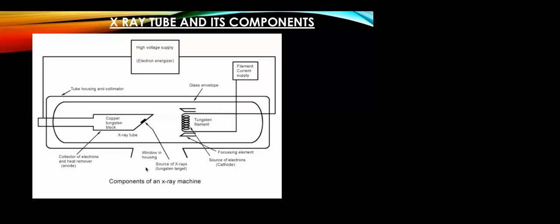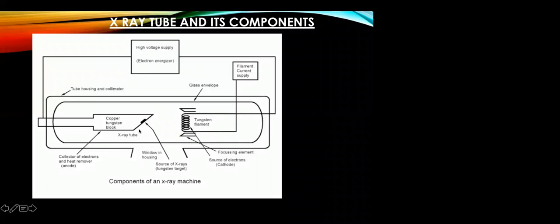This line diagram of the X-ray tube shows the spiral tungsten filament — the cathode or negative terminal — attached to a high-voltage supply so that electrons produced from the cathode can be accelerated through high voltage and target the anode. The anode is beveled, housed in a copper-tungsten block. Copper is used for rapid heat dissipation so that the anode does not get overheated. There is a tube housing and collimator, with a window in the housing to allow X-rays to move out of the tube. All of this is placed in a glass envelope.